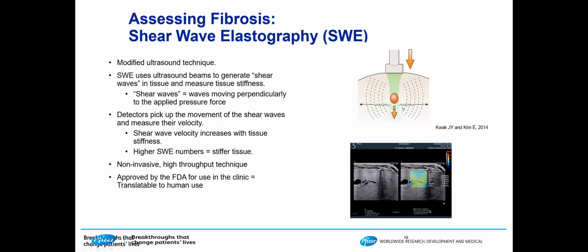and also the speed of the shear wave travel across the soft tissue can be used to calculate what's called an E modulus, which tells us how stiff the tissue is. So basically, if the tissue is stiffer, the shear wave velocity is going to be higher, because it travels very fast in a stiffer tissue. So in a normal tissue, the shear wave velocity is low. However, once the liver tissue starts accumulating fibrous content, the shear wave velocity changes proportionately. So basically, you're looking indirectly at the stiffness of the tissue, which is used as a surrogate marker for fibrosis.